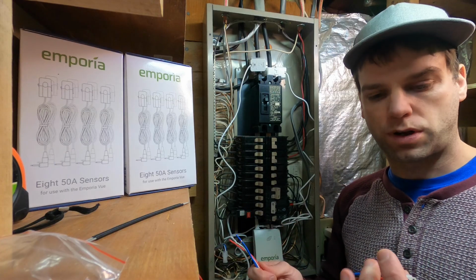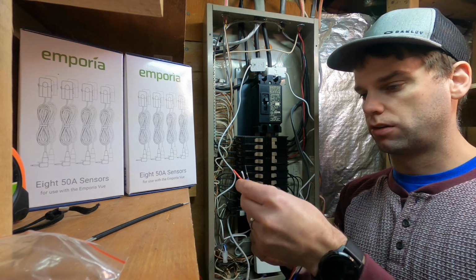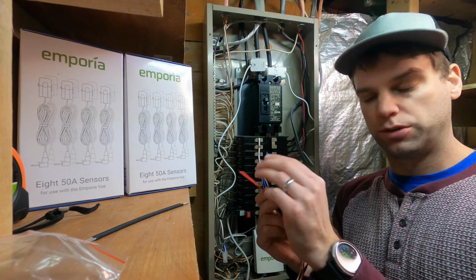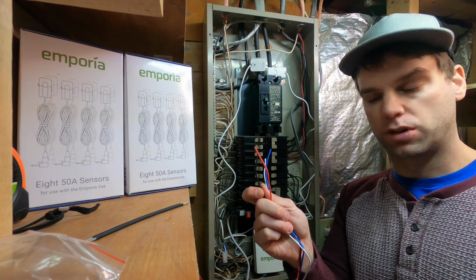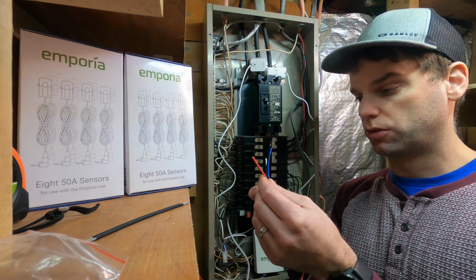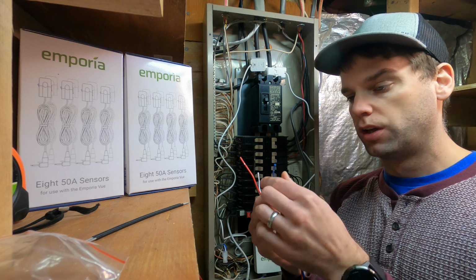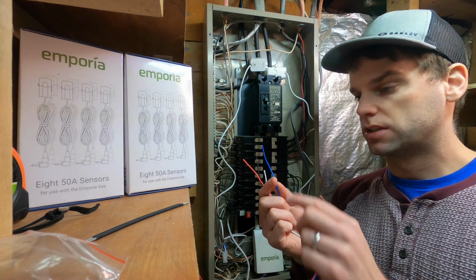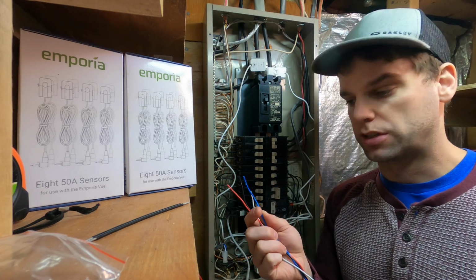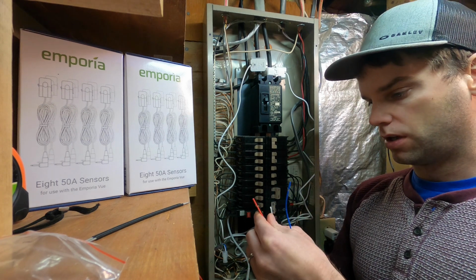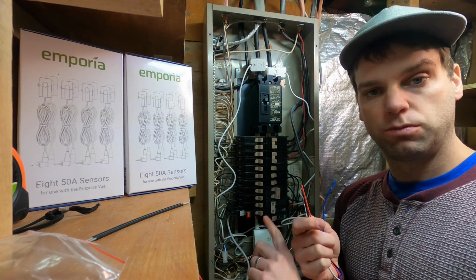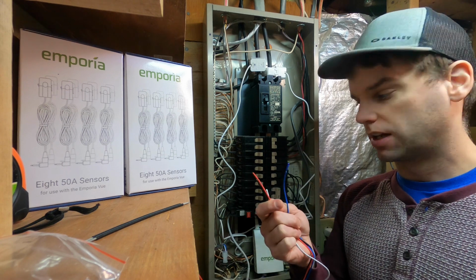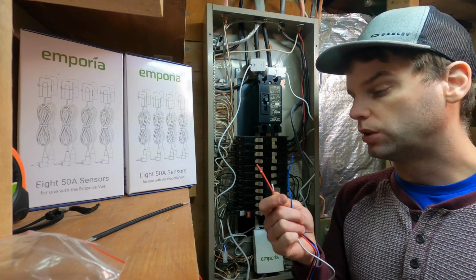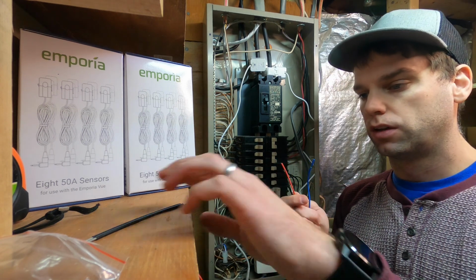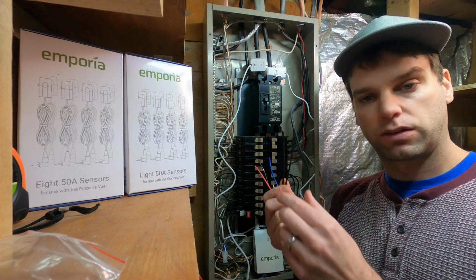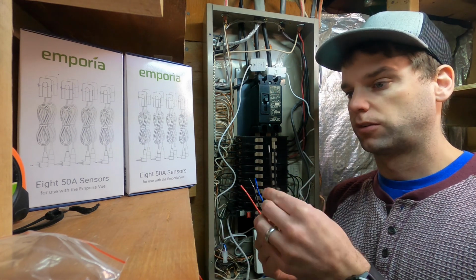So the way that they want us to wire this power, like I said, we've got four wires. We've got white, which is our neutral. We've got black, which is one of our 120 volt lines, red, which is our other 120 volt, and blue would be our third. But since we're not using blue, because we don't have three-phase power, the blue is also going to go on the neutral bus bar. And because I don't have two empty breakers next to each other, these are going to get pigtailed into existing breakers. It's really important that these go into 15 amp breakers, because the jumpers that they gave us are only rated for 15 amps.